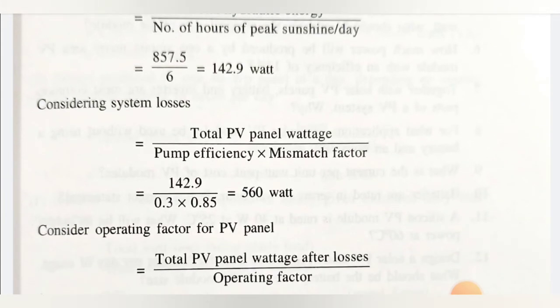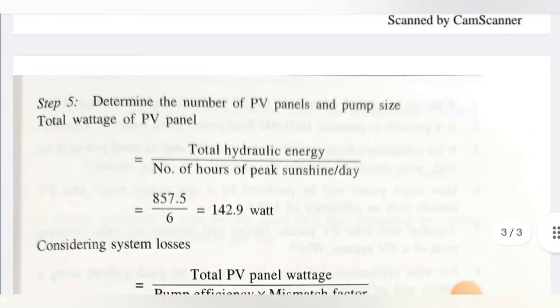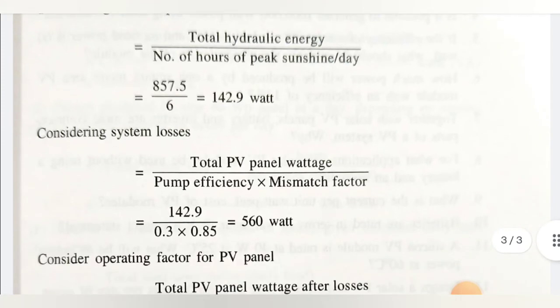Now considering system losses — pump efficiency and mismatch factor. Total PV panel wattage after losses = 142.9 W ÷ (pumping efficiency × mismatch factor) = 142.9 ÷ (0.30 × 0.85) = 560 Watts. Then considering the operating factor for the PV panel: 560 W ÷ 0.75 = 747.3 Watts of solar panels required.